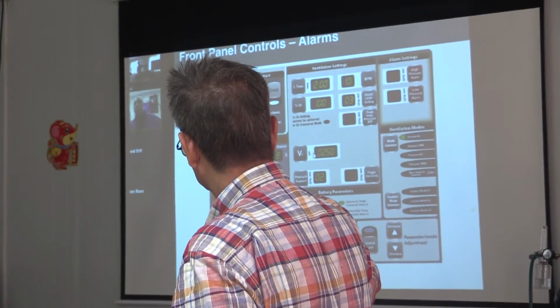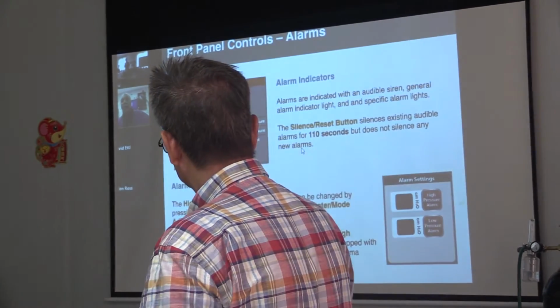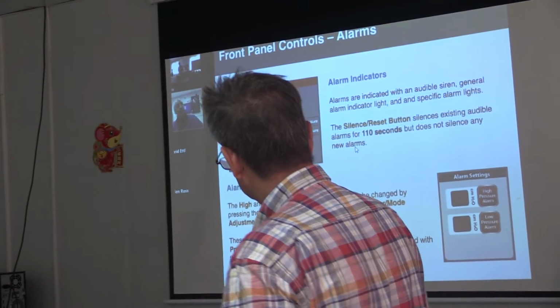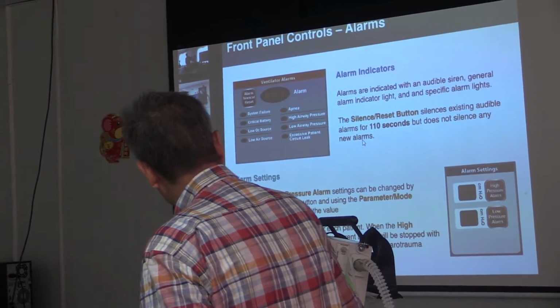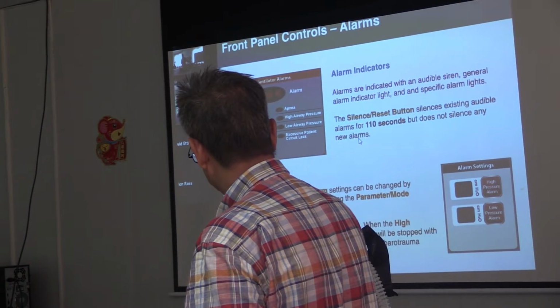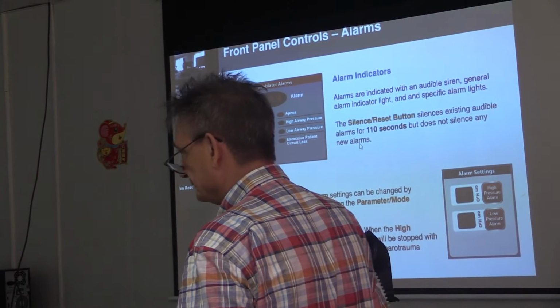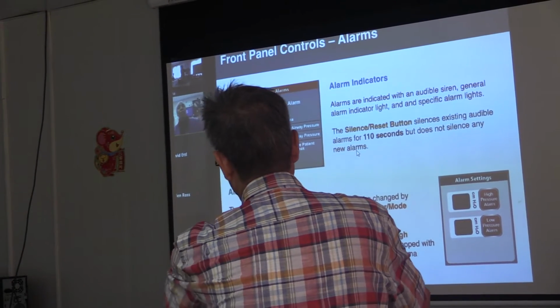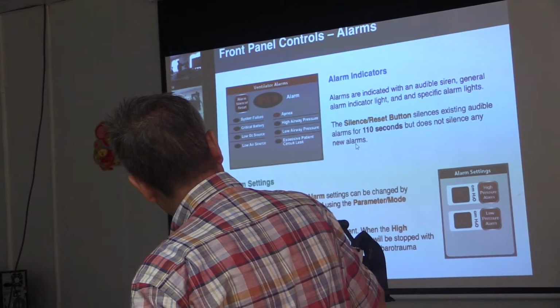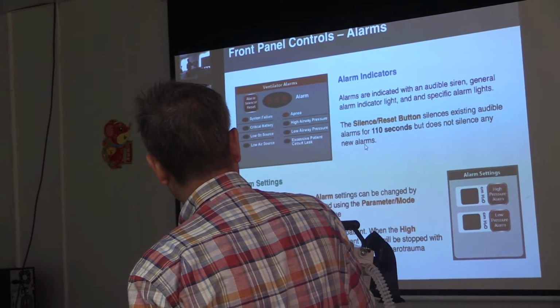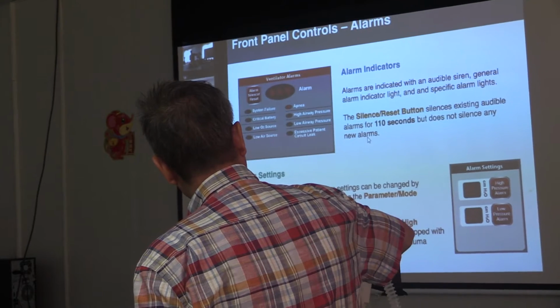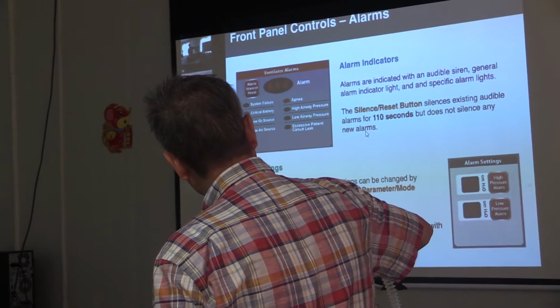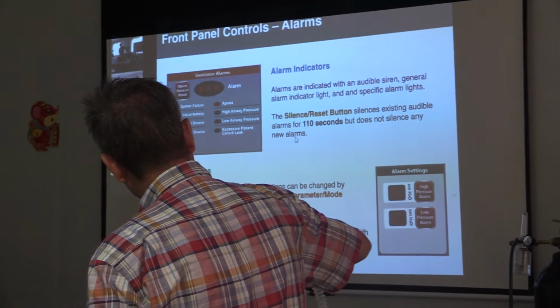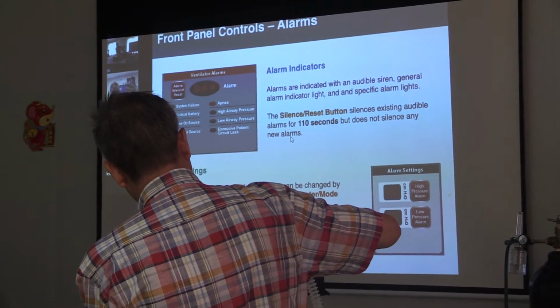Okay, so this slide is the front panel. You see the alarm setting area up in the upper right-hand area. We're going to cover that just a little bit. Sometimes the reason the ventilator is alarming is because you need to change the alarm settings. It may well be that your patient takes more pressure to ventilate than what the high alarm setting is set for. So the high pressure alarm is looking at what the peak pressure is.